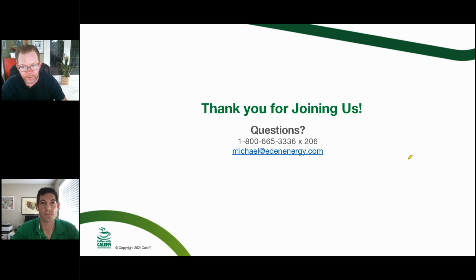Yeah, and obviously check the manual. We're assuming you're using Caleffi products, but check the manual. Depending on whose product, it could be quite a bit more. There are valves out there where you have to add another 9 degrees to that number to get effective mixing on that valve. So you want to pay attention to that for sure.